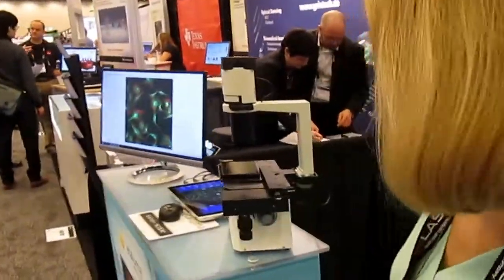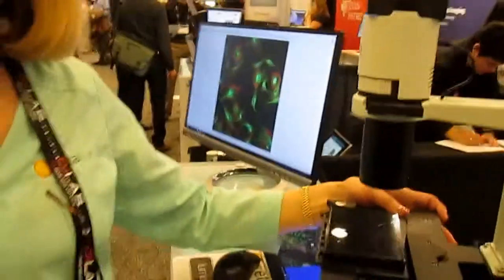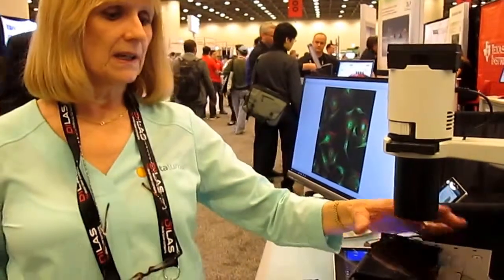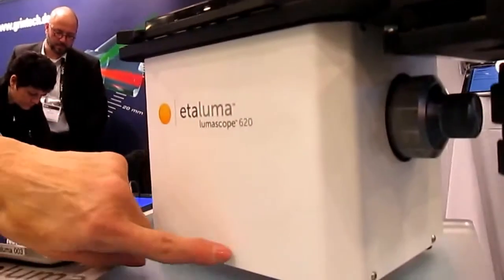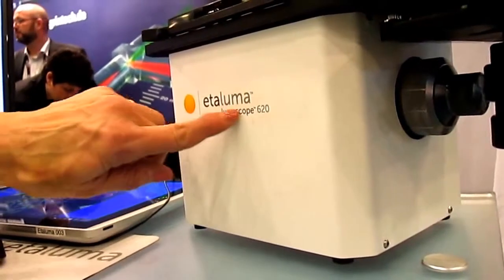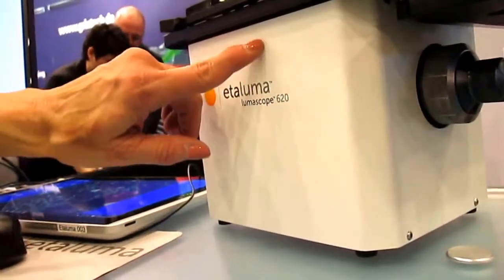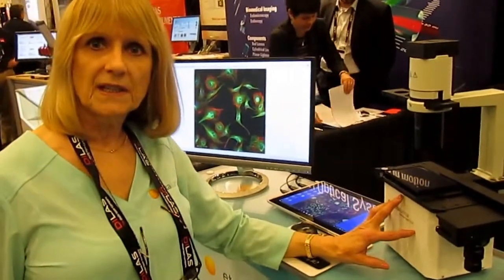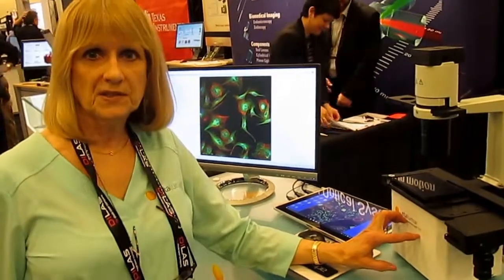So let's look at one of our manual ones. This is our Lumascope 620, and it does 3-color fluorescence. It is inverted. The optics are very simple. If you want to show the optics over here. So there's a camera at the bottom, then there's the light block, there's a photo tube, and then there's an objective. So by having this so simplified, and it's also solid state, we get very high resolution, as good as what you would get on a Zeiss or Nikon or other type of upright microscope. We retain about a majority of the light as opposed to losing it, which you get on a traditional microscope.